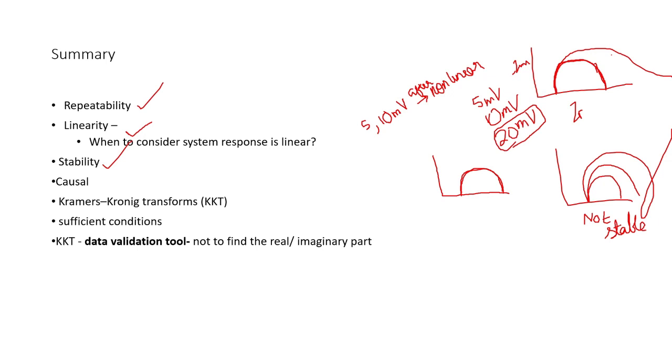I think repeatability is: if you take an identical sample with an identical solution and repeat the test, you are supposed to get the same results. That's what I told now. When I'm doing repeatability, I'll be changing my electrode and the solution. The entire system will be changed, in the sense of a fresh, identical one. Yes, that's what I meant. Sorry if that's not clear.